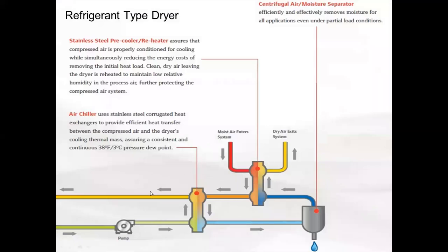Okay, so this is coming out of the glycol side of the heat exchanger in the first tank. Here's our little pump. It pumps through this heat exchanger. And on the other side of the heat exchanger, this is where our moist air stream enters. This is the heat exchanger that pre-cools it. So it comes in hot, it goes through this heat exchanger, and it's pre-cooled on the other side with the air that's leaving the dryer, which is cold, 35 to 38.